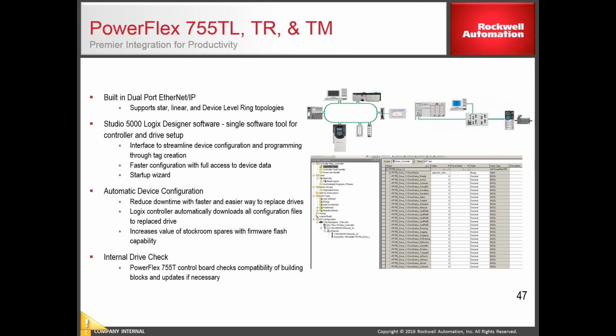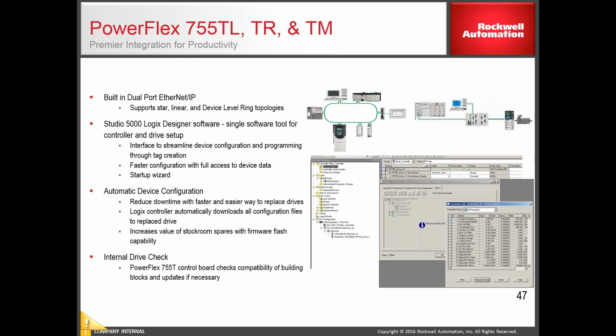So again, we'll have built-in dual Ethernet ports on these drives. Again, the whole premier integration story, working with ControlLogix, and you can set the drives up in a ring, just extremely reliable, easy to start up. We've got startup wizards. We use Connected Components Workbench now, which is a free software package that you can download from the Rockwell website, and you can use that to commission the drives. I mean, obviously, if you've got a HIM module, you can use the HIM module to set the drives up, but we do have a newer software package that we use to configure these drives.